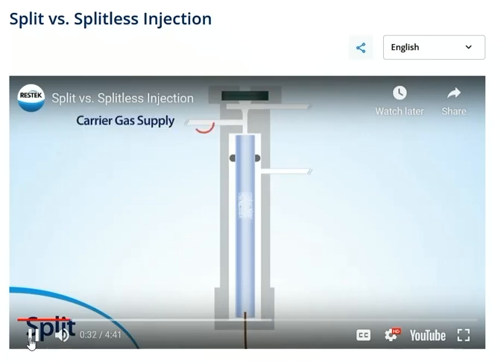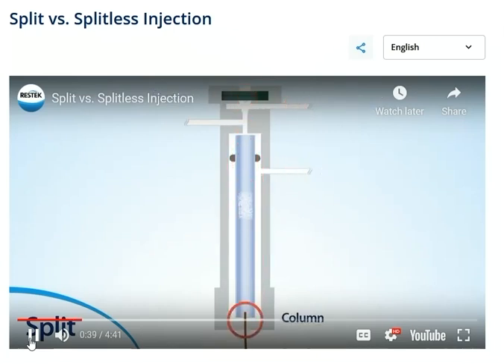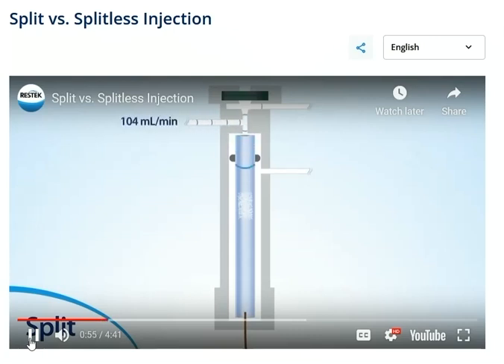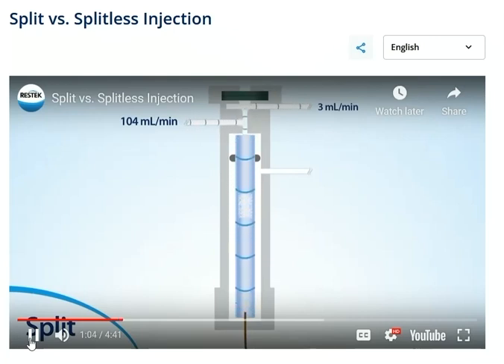Inside a split/splitless inlet, you will find the carrier gas supply, the septum, the septum purge, the split vent, the liner, and the column. Now we'll start the gas flow and simulate a split injection. The gas entered the inlet with a total flow of 104 milliliters per minute. A small amount — 3 mils per minute — passed through the septum purge to reduce possible contamination from the septum, while the rest continued onto the liner.